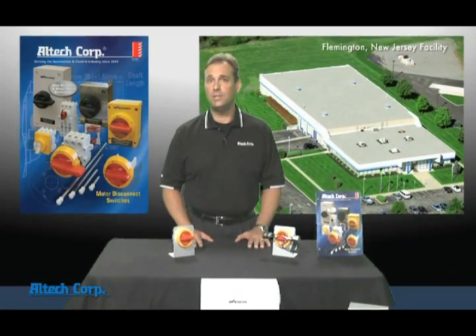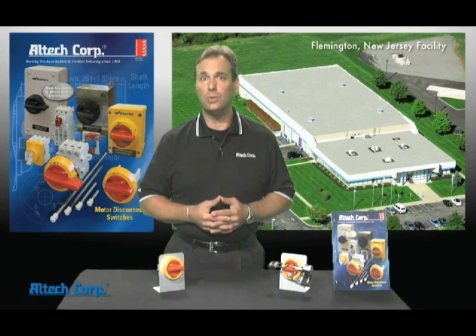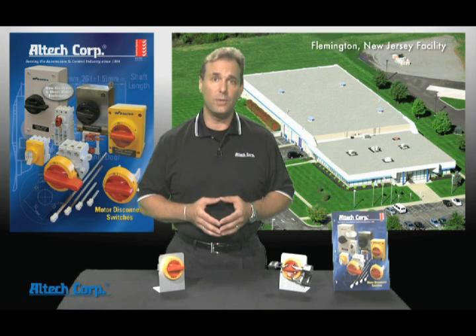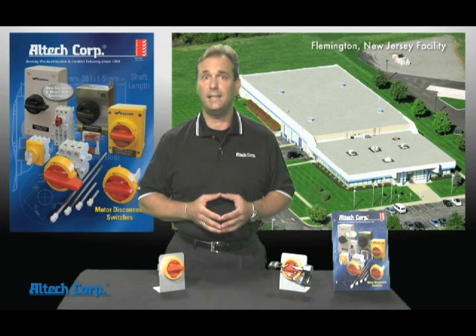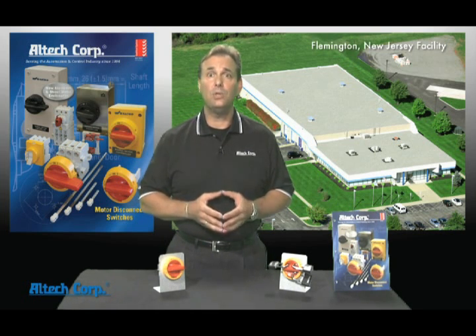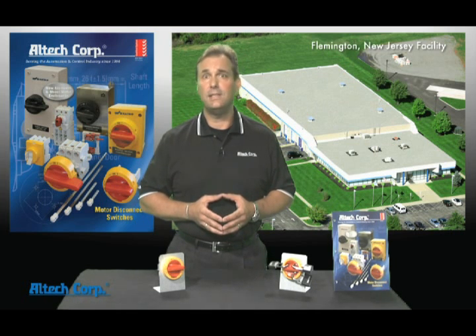Altech offers a full line of motor disconnect switches. These are true UL listed manual motor controllers with disconnecting means. All of our switches are built with advanced switching technology utilizing silver contacts rated 16 to 150 amp at 600 volt, and across the line motor starting up to 75 horsepower. We have a full line of self-contained switches with enclosure choices of polycarbonate, aluminum, sheet metal, and stainless steel.